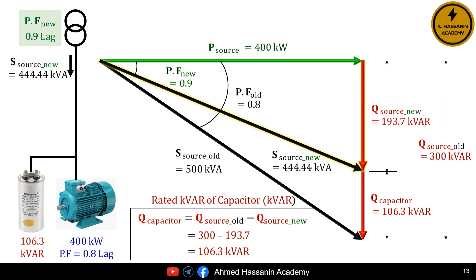So the reactive power of the capacitor Q capacitor, required to correct and improve the power factor of the source from 0.8 to 0.9, is equal to Q source old minus Q source new. Therefore, Q capacitor equals 300 kilovars minus 193.7 kilovars, which equals 106.3 kilovars.